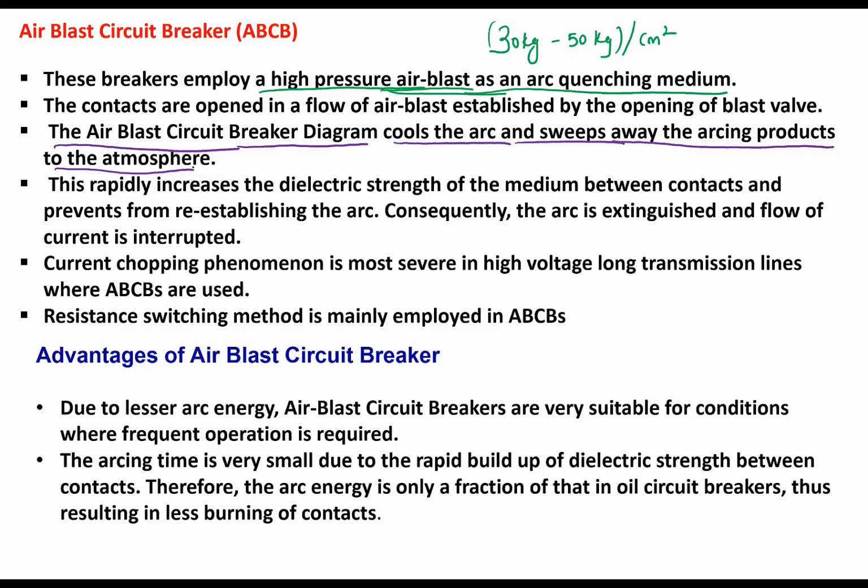So when the conducting particles are swept away between the fixed and moving contact, the air regains the dielectric strength between the contacts and thus prevents re-establishing of the arc. Once the charged particles through which the arc is sustaining are swept away, then what happens? Again, the natural air replaces between the fixed and moving contact, which increases the dielectric strength. Consequently, the arc is extinguished. Understand?